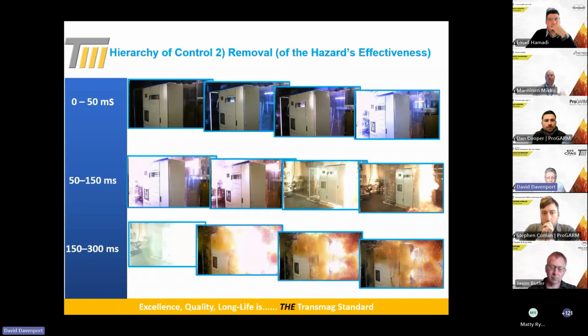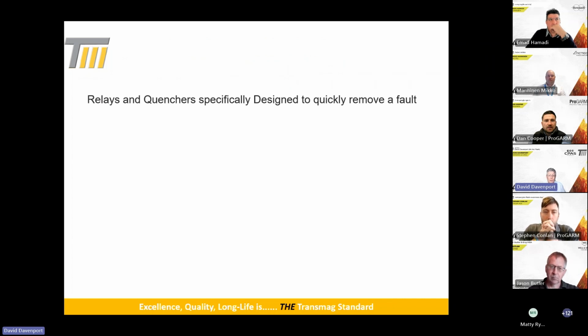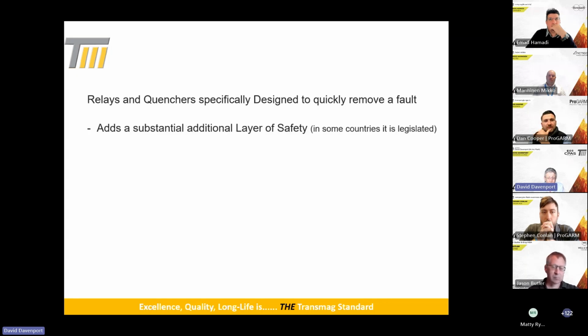Number 2, how do we prevent that occurrence? Removal of the hazard's effectiveness. When we look at arc protection, relays and quenchers are specifically designed to quickly remove a fault. It adds a substantial layer to safety, and in some countries it is actually legislated. If you look at the USA, parts of Scandinavia, and it's creeping more and more into Europe now, the technical capability of preventing a dramatic arc flash explosion should be part of the features you include when you design a switchboard.